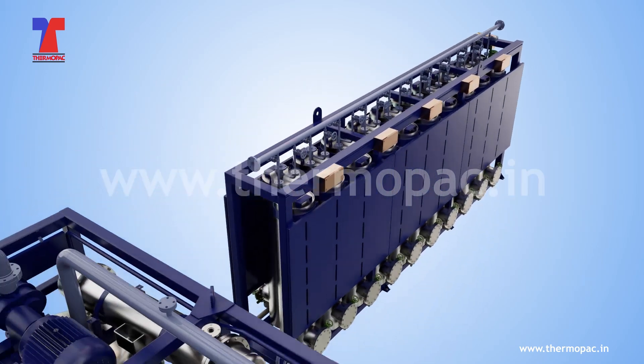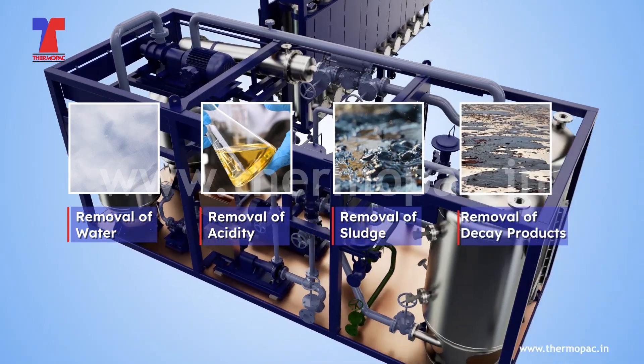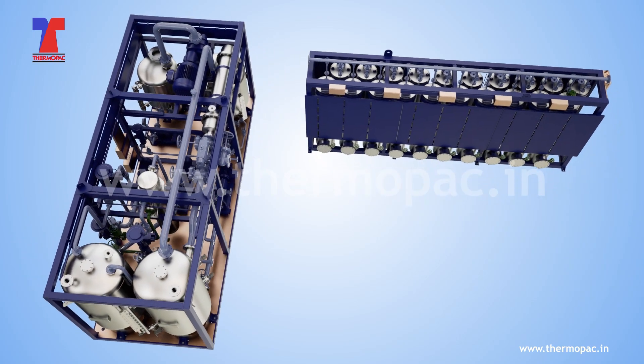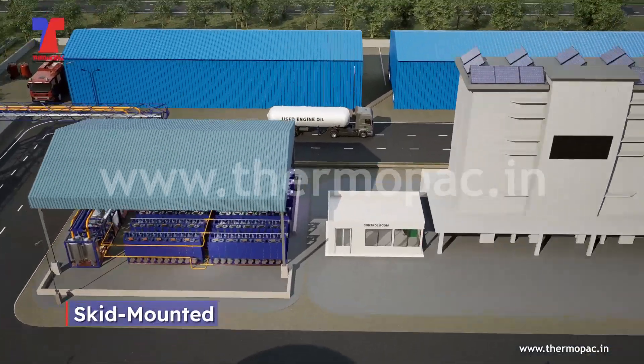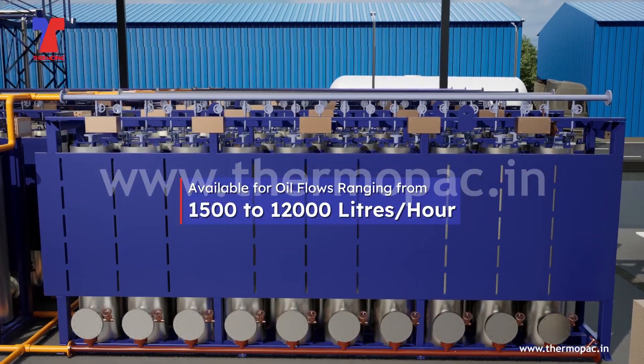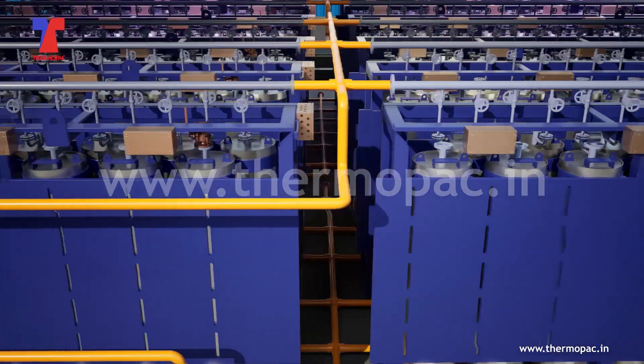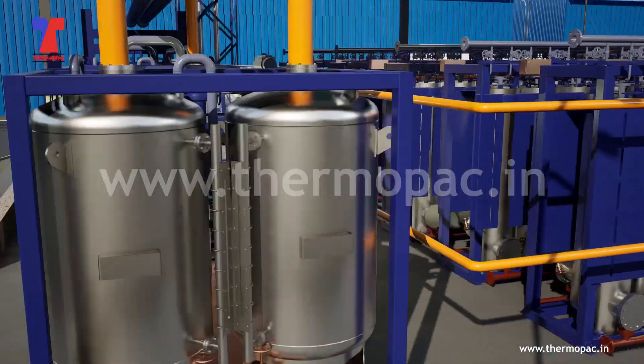In regenerating insulating oil by removing water, acidity, sludge, and decay products, resulting in oil with superior oxidation stability and reduced gassing tendency. Thermopac plants are skid-mounted and available for oil flows ranging from 1,500 to 12,000 liters per hour. A unique feature of this plant is its ability to regenerate oil continuously using a cyclic program that reactivates.